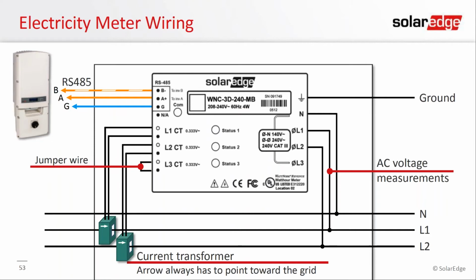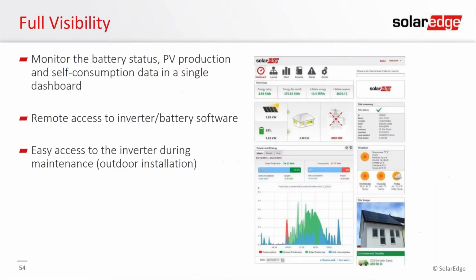So how do I install the StorEdge electricity meter? All I have to do is wrap these CTs around the feeders of the service entrance. I'm going to connect a power supply and get some voltage sensors. And then if this meter is installed next to the service entrance, I'm going to route RS-485 communication from the meter to the inverter. That has a maximum range of 1,000 meters or 3,000 feet. So that's why we want the SolarEdge electricity meter next to the service entrance. It just may happen that that's where your inverter is also installed. But I've seen instances where people put the electricity meter next to the inverter, and the inverter's in the garage on the other side of the house or in the basement, so far away from the service entrance, and then they ask, well, can I get extensions for my CTs? So it doesn't make sense to do it like that. Again, I can't stress this enough. Put the electricity meter next to the service entrance.